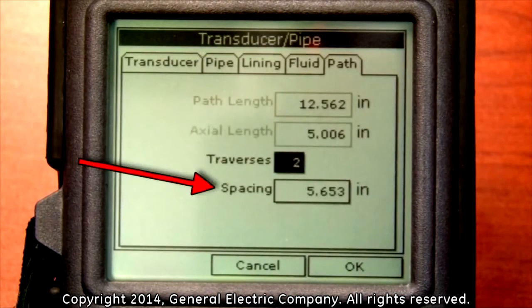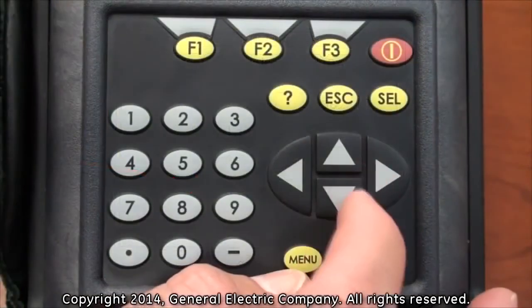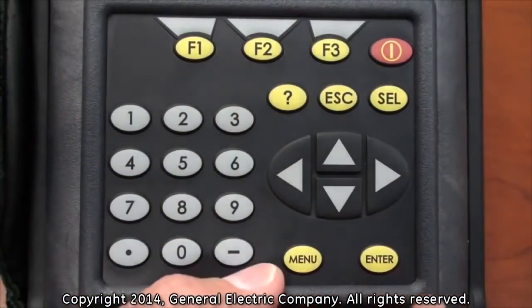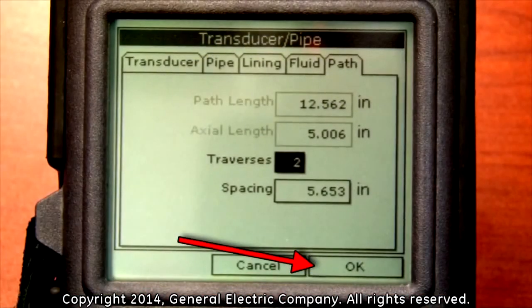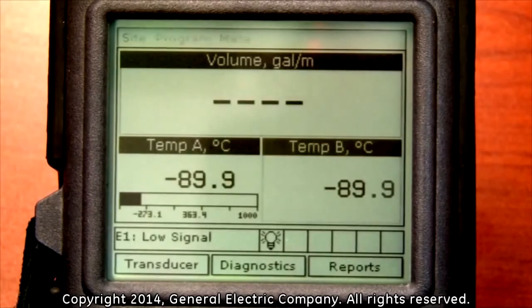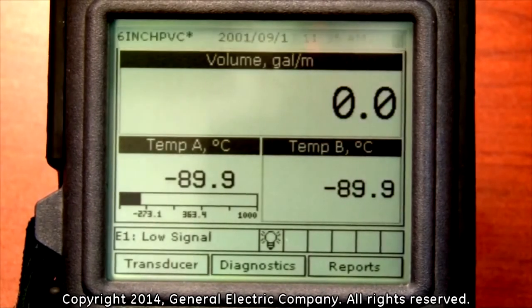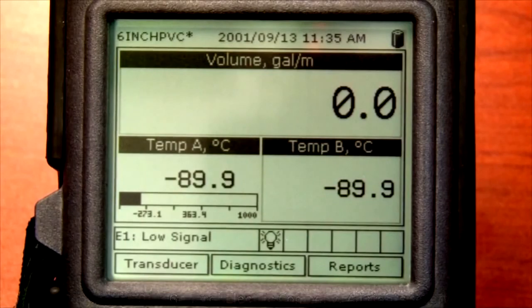The spacing for the transducer separation will be automatically calculated for the number of traverses. Once the transducer spacing is calculated, write down the number you see in the spacing field, as this is the spacing you will need to use when mounting your transducers with the mounting brackets to your pipe. Press the F3 button, which corresponds with the OK message on the bottom right of the display screen. Your PT878 is now ready to read flow measurements from the programming parameters you have set.